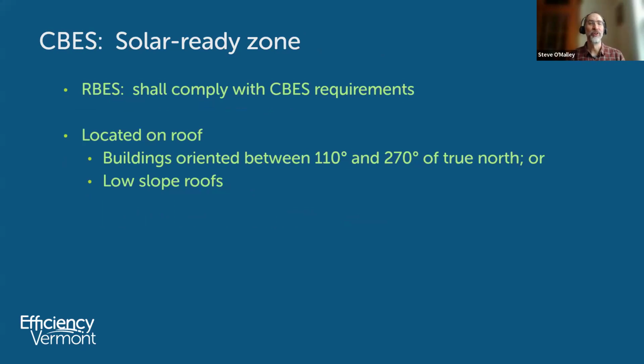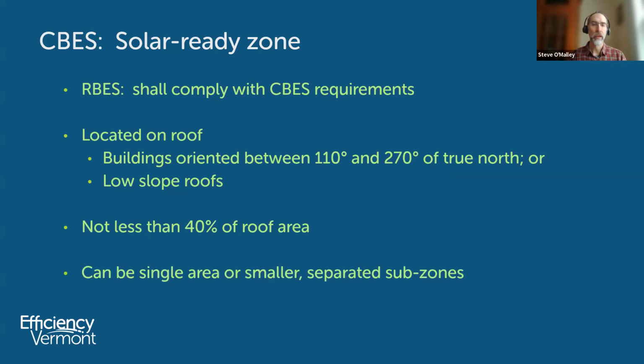All right, CBES, solar ready zone. This is great, we've got alignment between RBES and CBES, so it's the same requirement. The solar ready zone is described as being located on the roof, not on the ground anywhere or at an offsite location, for buildings oriented between 110 and 270 degrees of true north, or buildings that have low slope roofs. The code calls out that not less than 40% of the roof area shall be designated as a solar ready zone.